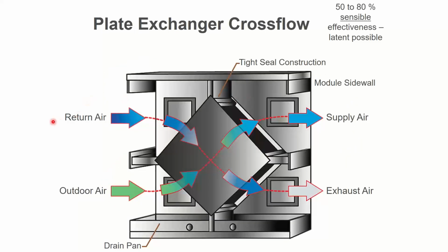Those guys work much like the wheel I showed you earlier. They crisscross the two airstreams though. So one airstream goes through this way, the other airstream goes through this way. Those airstreams don't touch. One guy warms up a metal plate, the other guy receives that heat. And then the airflow goes and warms the next plate up on that way. So I got like 5 channels, or actually more than that. I got 25 channels of airflow going one way and 25 channels of airflow going the other way.